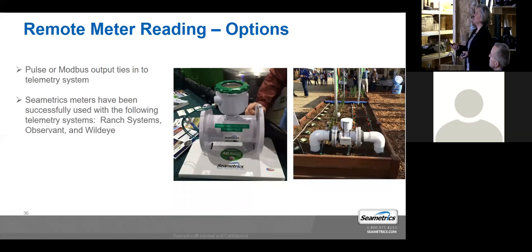Our meters were on display last week with Ranch Systems, Observant, Wildeye. Those were a few of them that had them tied in their booths, simulating what that would look like. So you can read meters remotely, yes. Even if you have an old-fashioned propeller meter or an old-fashioned mechanical meter out there, you can get remote technology on it. You call that meter manufacturer up, let them know what you want to do. Typically they'll sell you a pulse output transmitter that you would mount under the register on that meter. And then you want to make sure that that pulse signal is going to be compatible with whatever manufacturer you're looking at partnering with. So it's pretty amazing, but it doesn't matter how old your meter is, what brand it is, or what technology it is, you can read those remotely now.